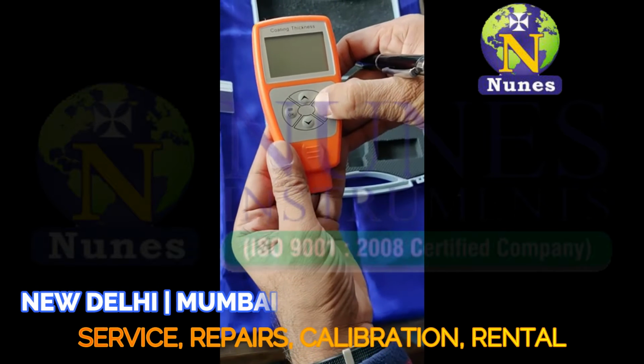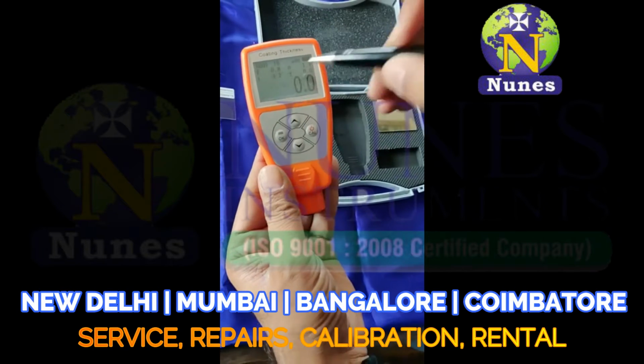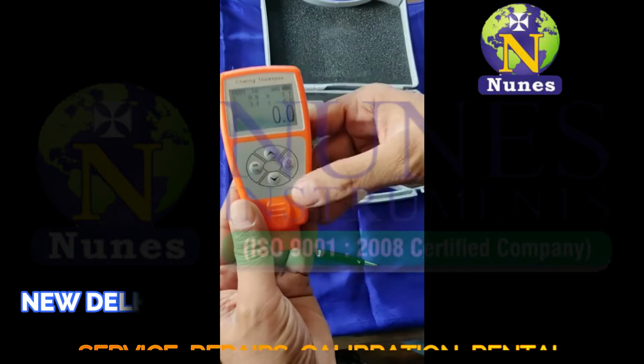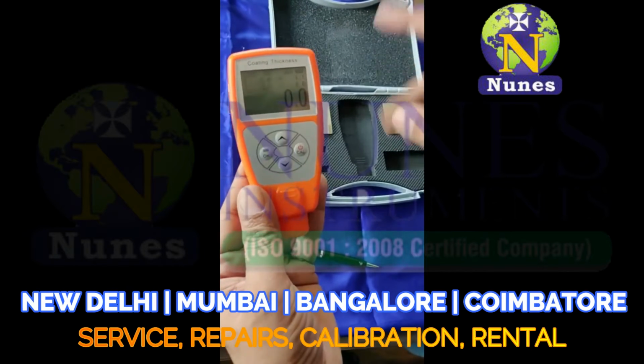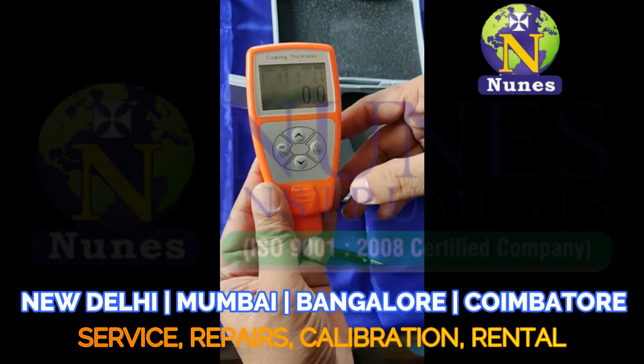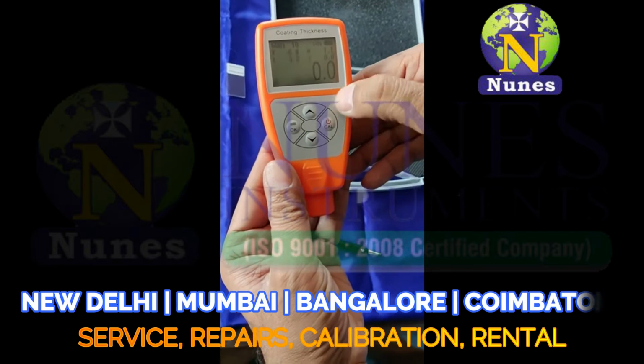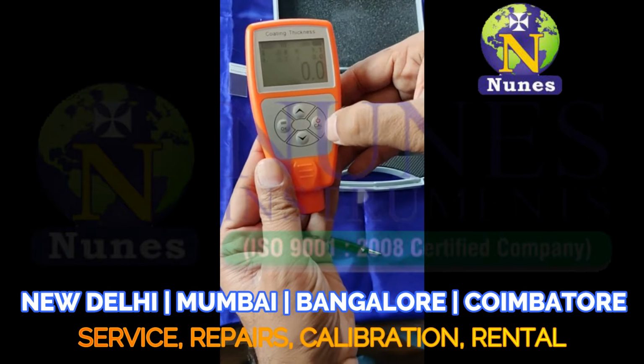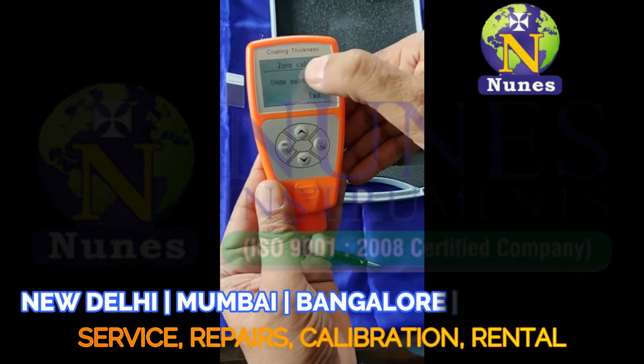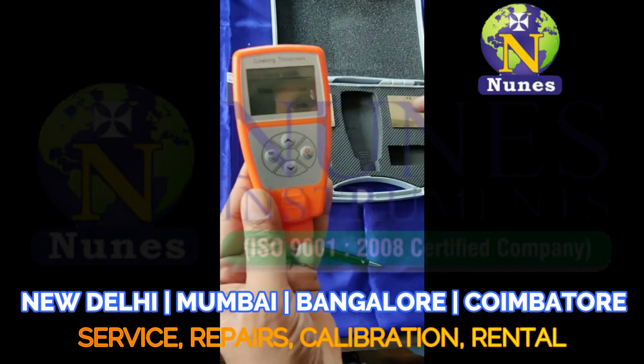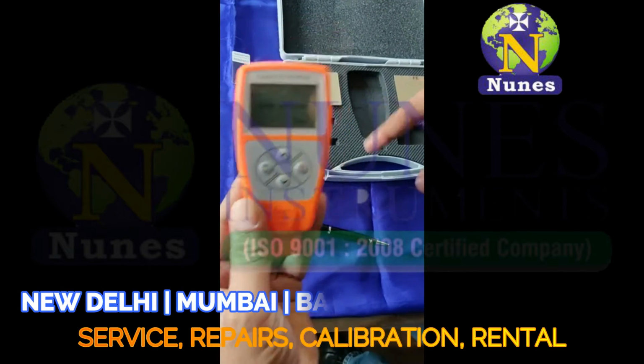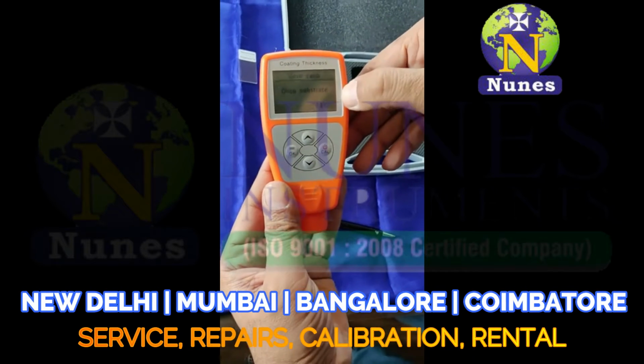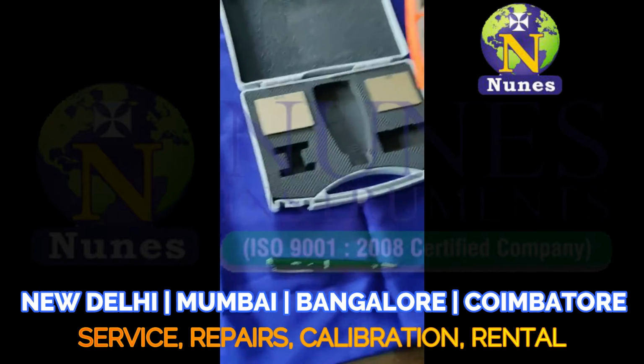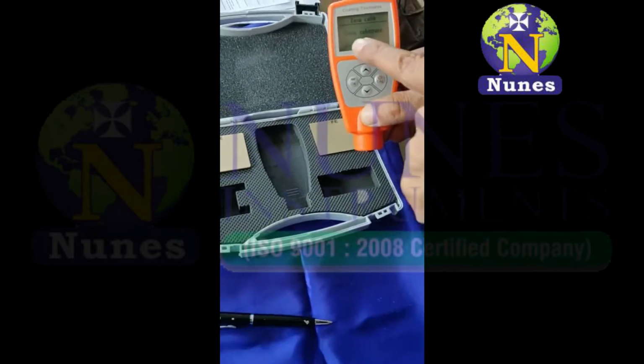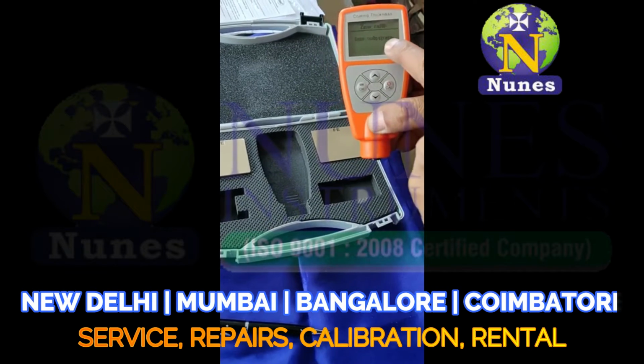So we first switch on. It says CTG 801. There are a few types of calibration, and first we'll show you all the different types. First we press this particular button which says cal. When you press cal, it says zero calibration, which means calibration on a coating gauge onto the substrate with no foils. It is very user friendly. Everything will be mentioned here. So it says right now onto substrate.